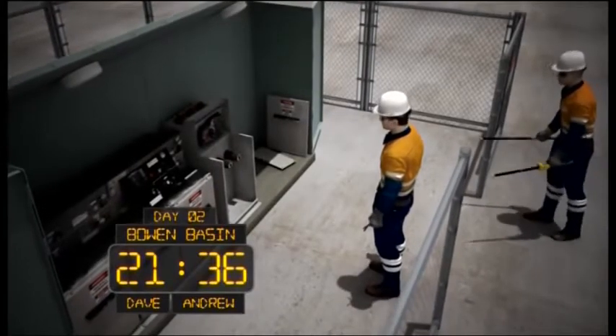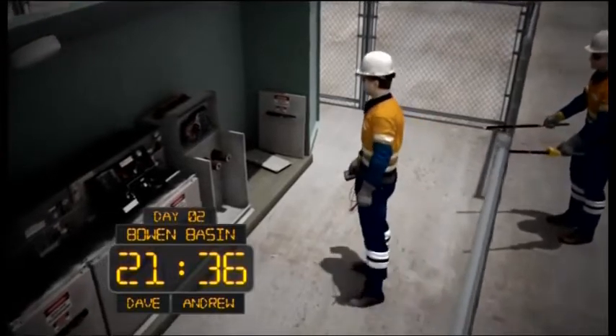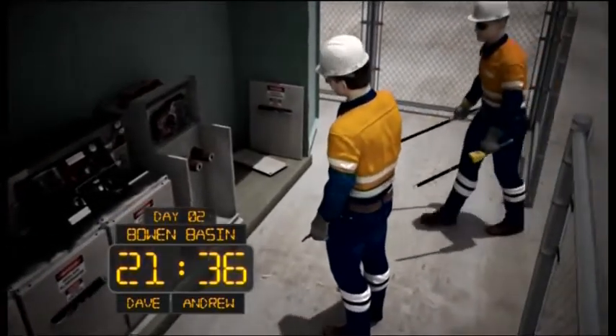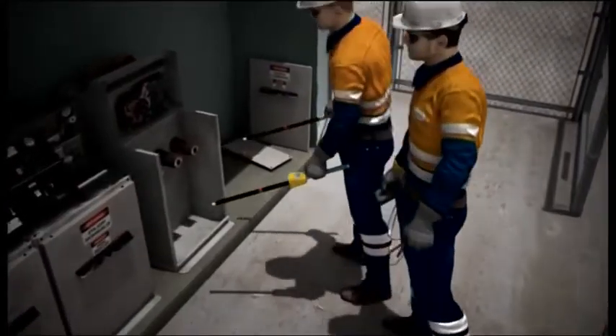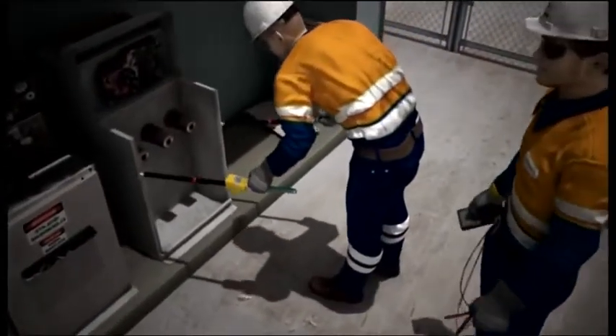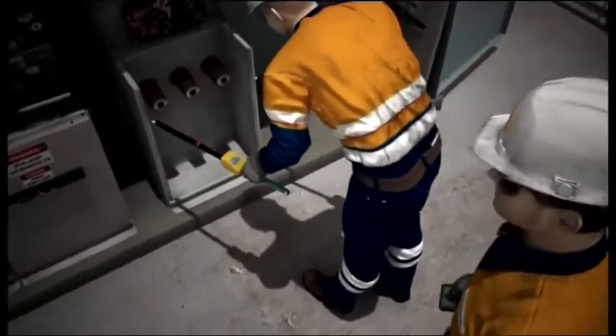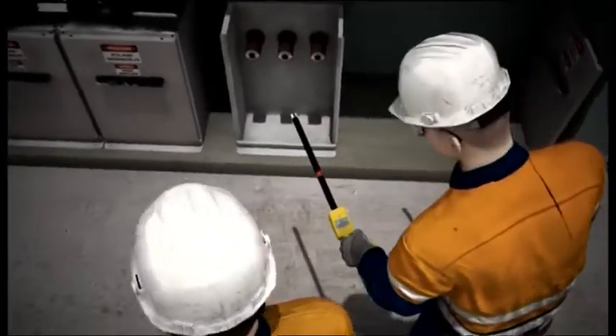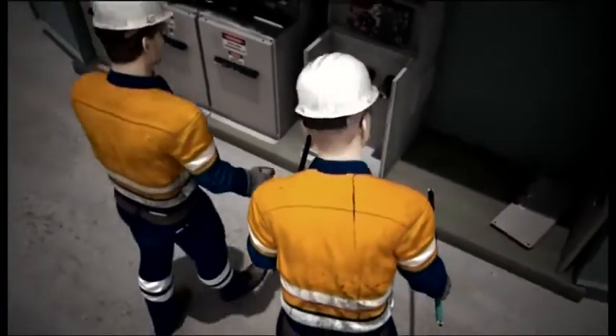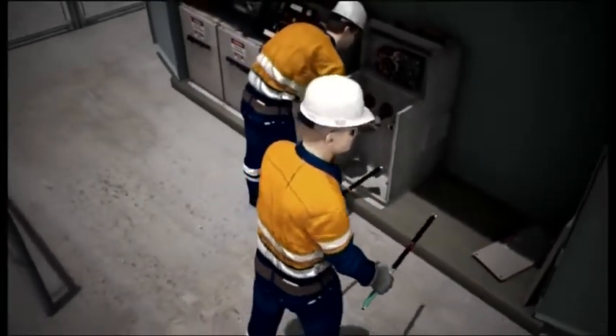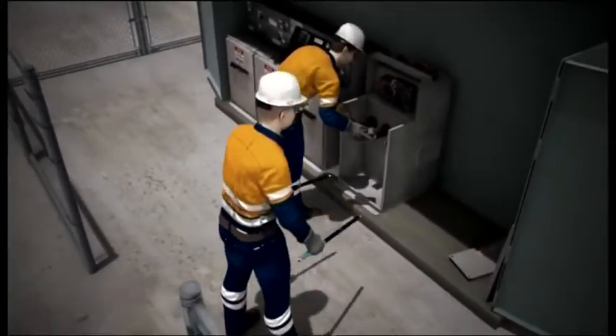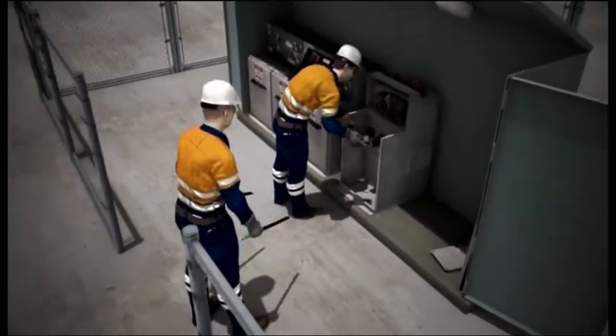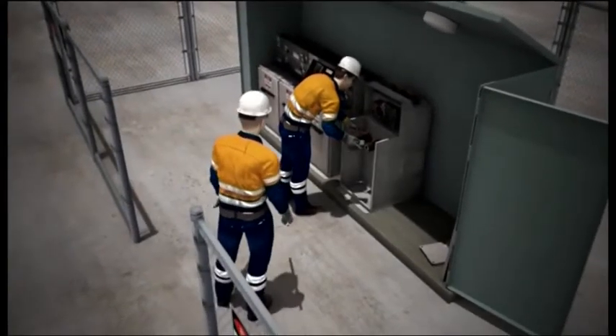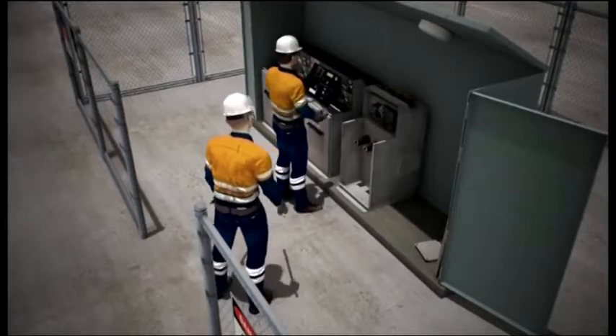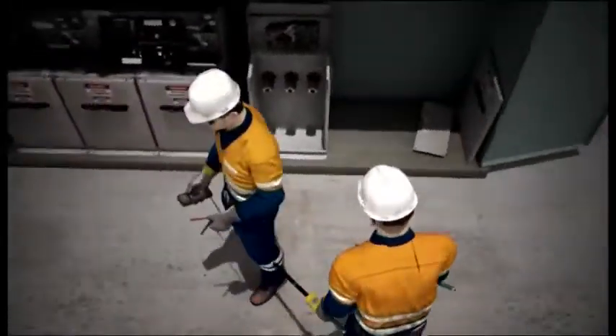Andrew returns from the workshop with a non-contact testing device to test the three-phase spouts for any high voltage in the cabinet. With the cabinet's cover now removed, he proceeds to test that the three 22 kV high voltage outgoing phase spouts are dead. The tests show that there is no high voltage present. However, approximately 20 volts is present. They detect this voltage with a handheld digital multimeter, which they use after the high voltage non-contact meter detects low voltage presence. They decide this is residual voltage that poses no threat.